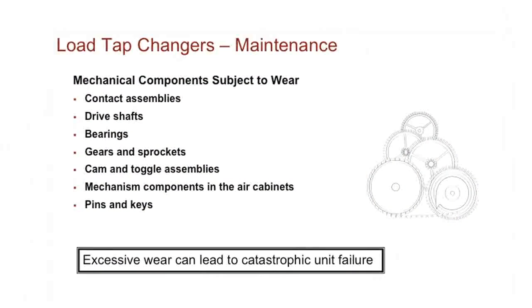Also, you have mechanical parts. You have the contact assemblies, the drive mechanisms, the bevel gears inside, cam switches, things of that nature that are all inside, that are the mechanical side of it. May be inside the tap changer, it may be inside your motor drive cabinet. These components, whether they're the switches, the motor drives, are all different variations. We're talking about the mechanical parts of it. Basically, that you get wear, excessive wear on your component parts, so you've got to identify those as well when you're doing your inspection. Another big item is the oil inside.